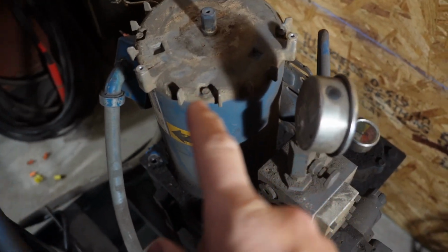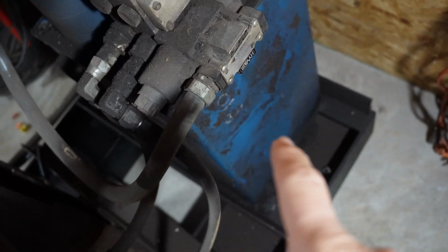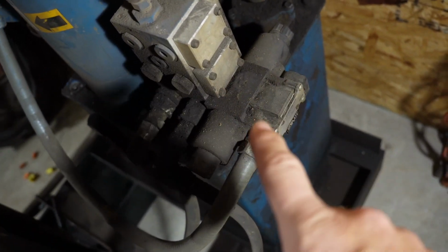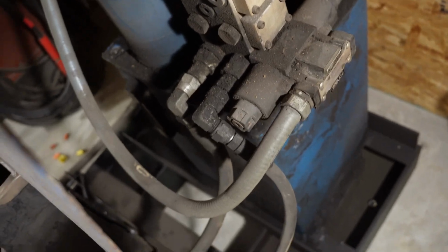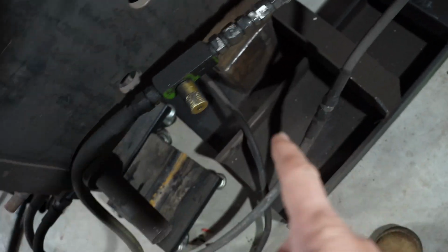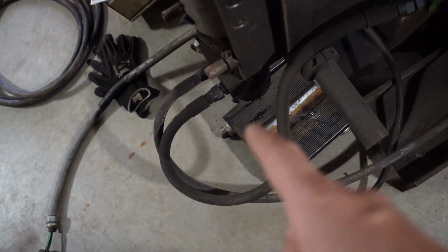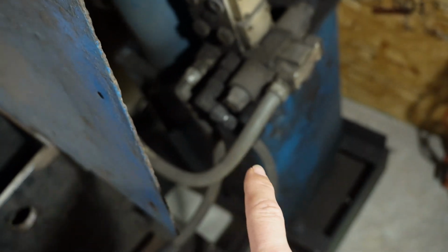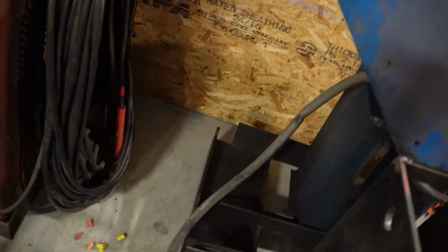So we got our 3-phase motor driving an electric pump that's down there in that tank. Then we've got this shuttle valve here, a solenoid operated hydraulic shuttle valve. And then you can see we got hydraulic hoses going to and from a hydraulic motor that spins the entire chuck. So basically when you hit the pedal, it takes power from there, routes it through that transformer, sends that power up to this shuttle, opens the valves that allow hydraulic fluid to go to and from the hydraulic motor, all in one shot. Yeah, pretty busy.